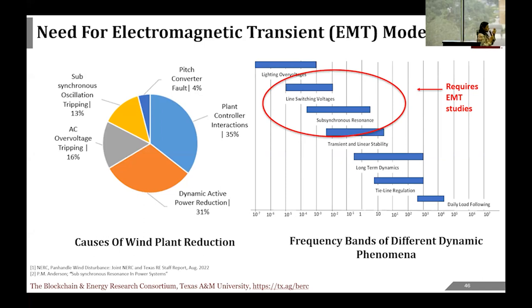ERCOT and NERC sat together, prepared a report, and analyzed the causes. The root causes were plant control interactions, AC overvoltage tripping, and sub-synchronous oscillation. Sub-synchronous oscillation occurs because a transmission line modeled as an R-L circuit is often series-compensated with a capacitor, forming an RLC branch. The frequency of oscillation is 1/(2π√LC), and when this sub-synchronous frequency matches a torsional mode frequency of the generator, it can lead to fatal failures. All these major concerns involved analysis in the millisecond-to-microsecond range, requiring EMT studies.